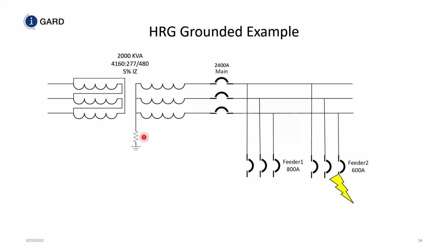Again, I'm showing my age because nobody has bread boxes anymore. We have the same ground fault. Actually, we changed phases on this particular fault. We're on C phase now. Now, when we have a ground fault, the ground fault current changes to 5 amps. It used to be 34,000 amps. Same transformer. Inserting a 55 ohm resistor limits that fault current to 5 amps. That means we don't have to trip.